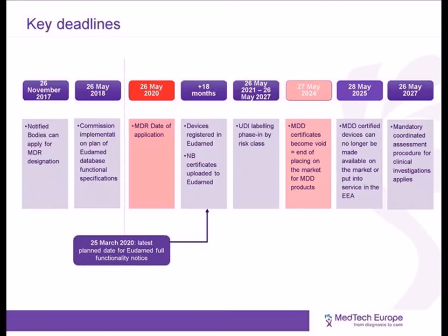Final point on this slide. The EU MDR introduces a centralized, coordinated assessment procedure for multi-country clinical investigations conducted in Europe. This procedure for multi-country clinical investigations becomes mandatory after May 2027 and will hopefully bring increased efficiencies to the clinical development process.